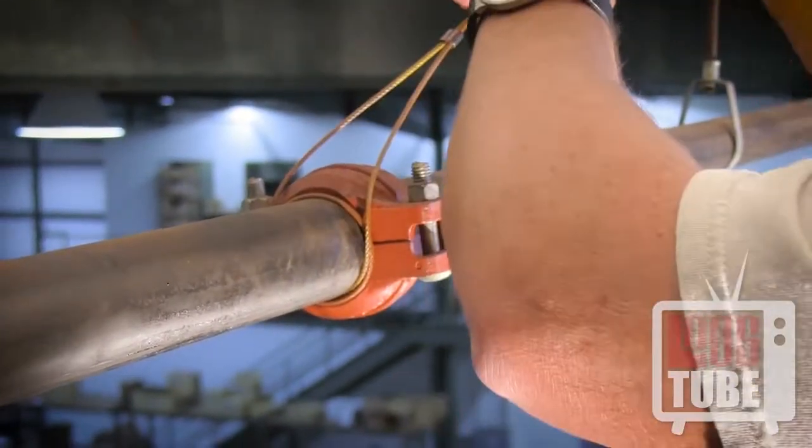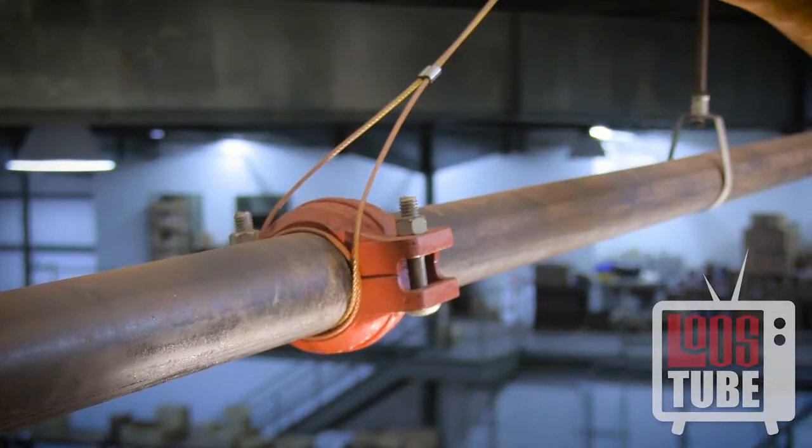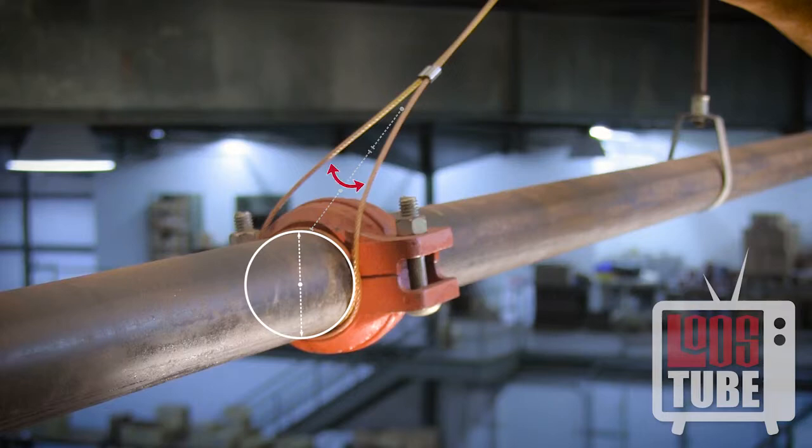Before you swage the fitting, ensure that the sleeve is positioned at a minimum distance of one and a half pipe diameters away from the pipe. This will ensure that the maximum 45 degree angle in the cable is maintained.